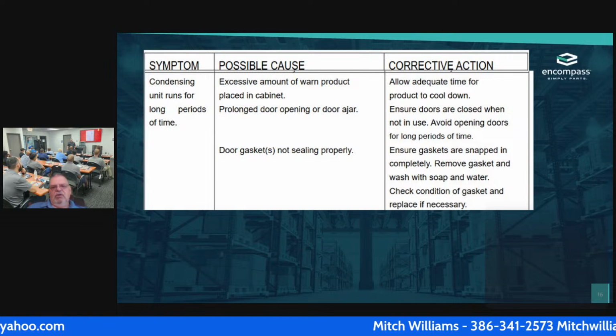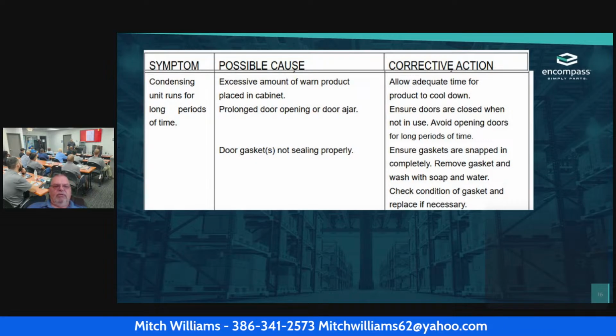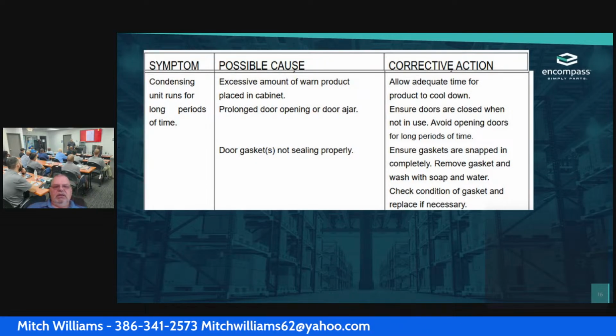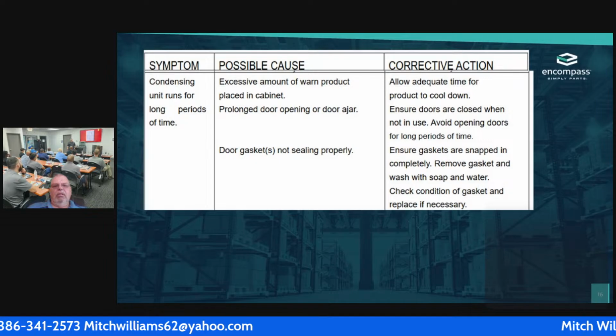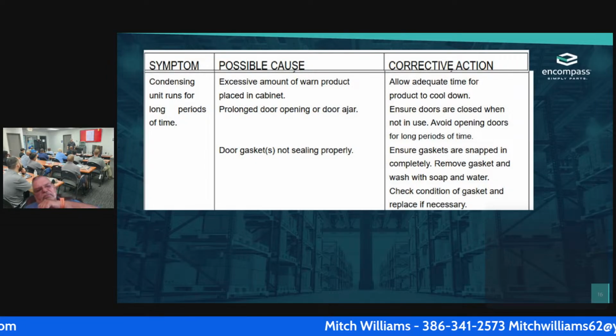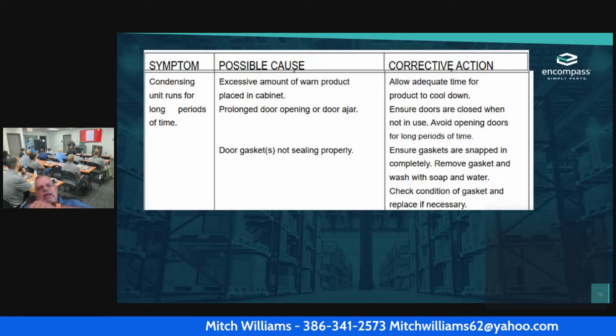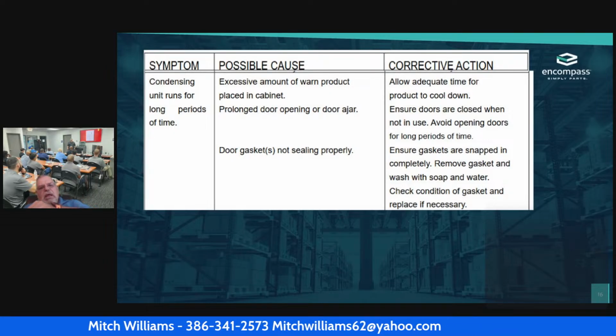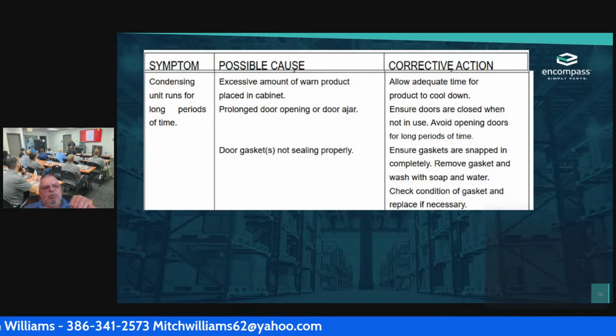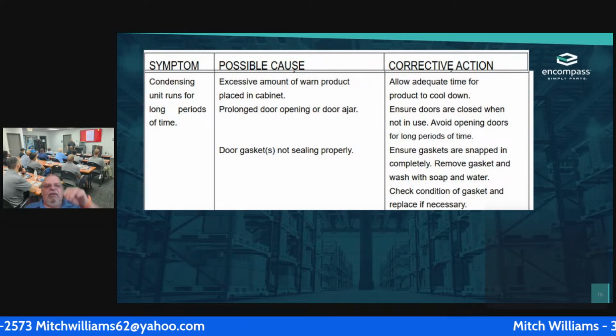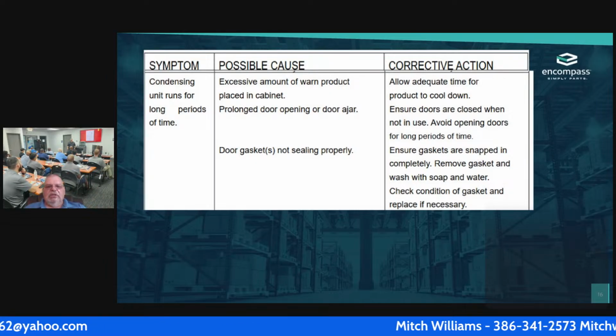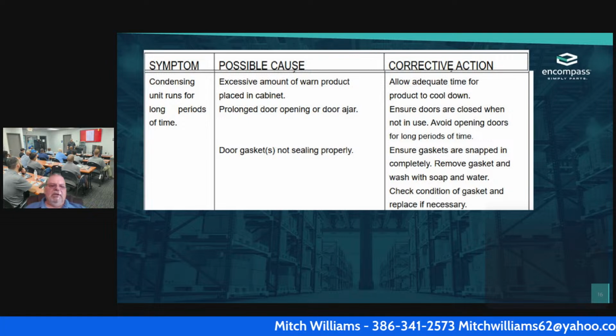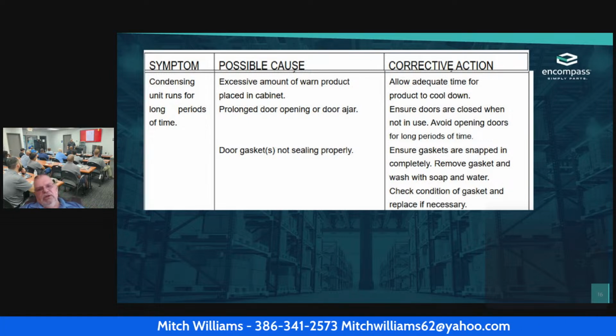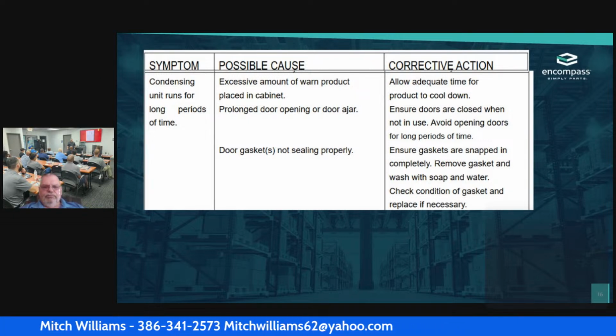So you're going to have to go... I don't know what you use to check the door gasket for sealing. What I use is a nice $1 bill. I open the door, stick my bill halfway through, close that door, and try to pull that dollar bill out. If I have resistance, I know that it's sealing. If it just slides right out, I'm going to need to adjust the gasket. Okay.